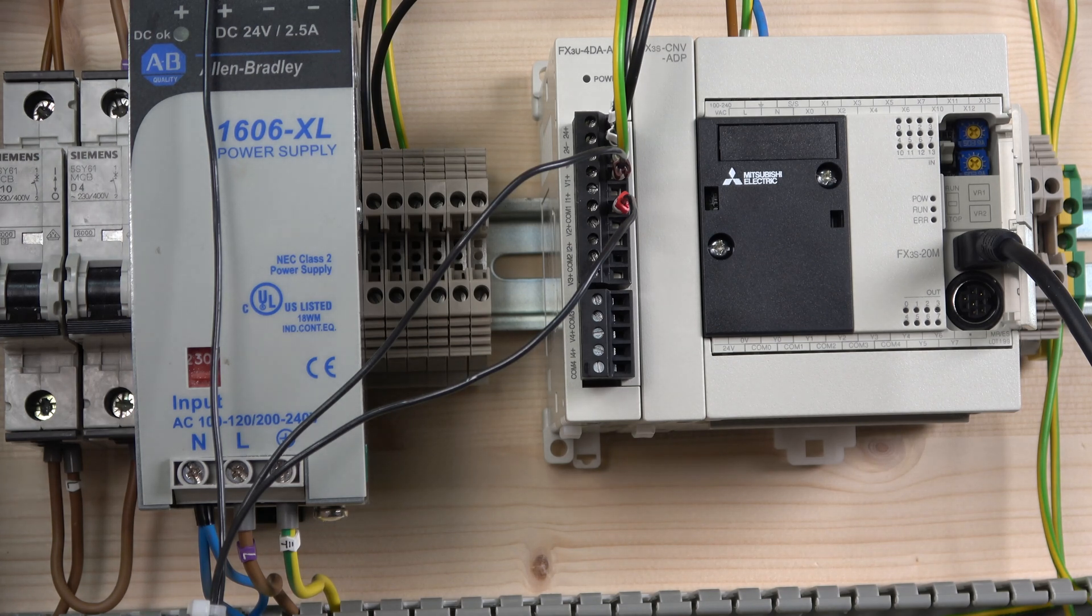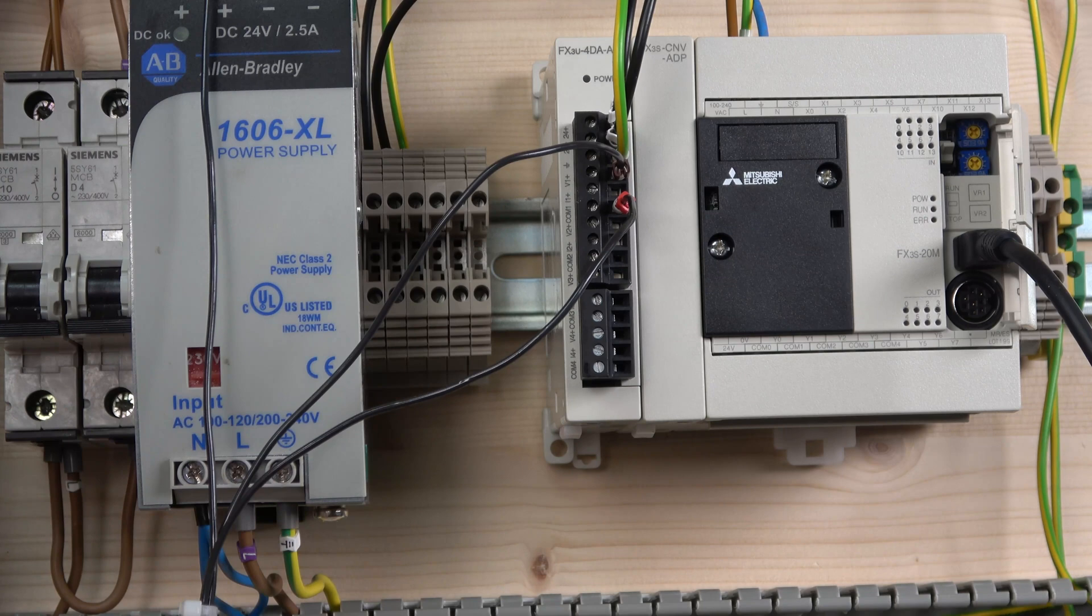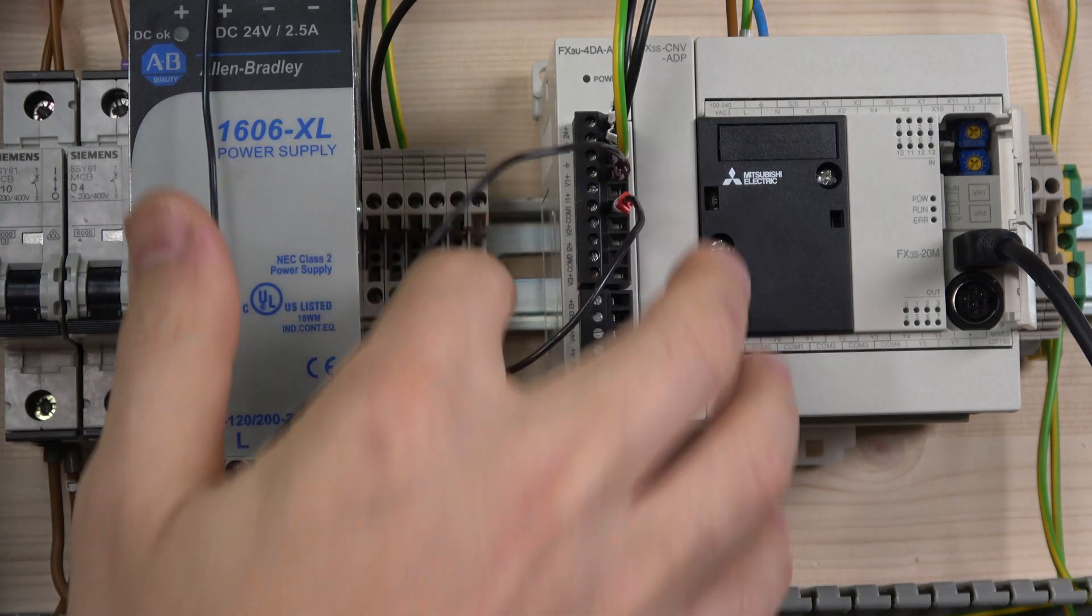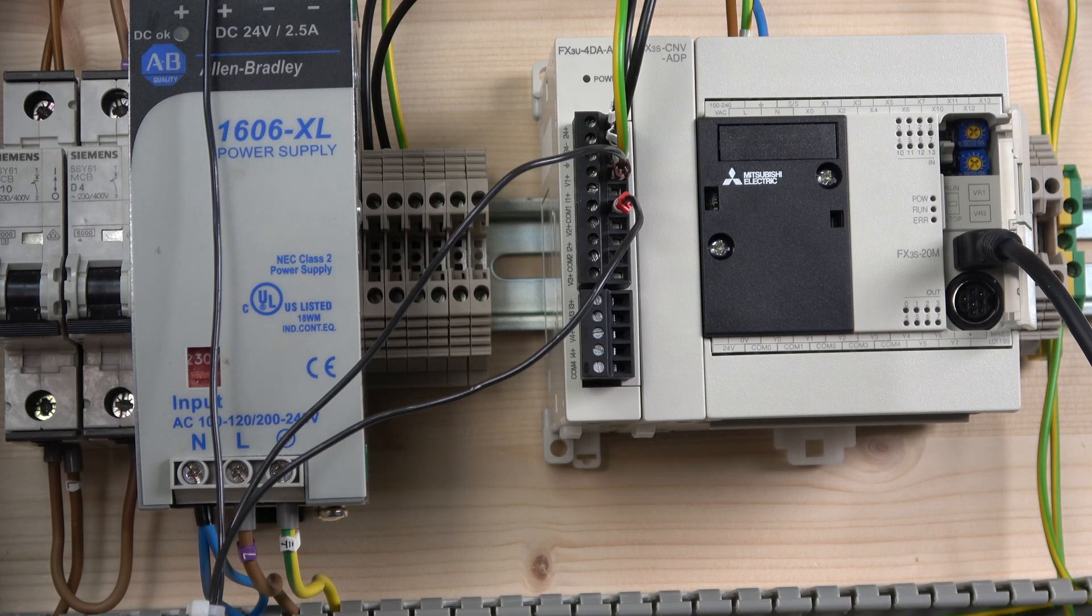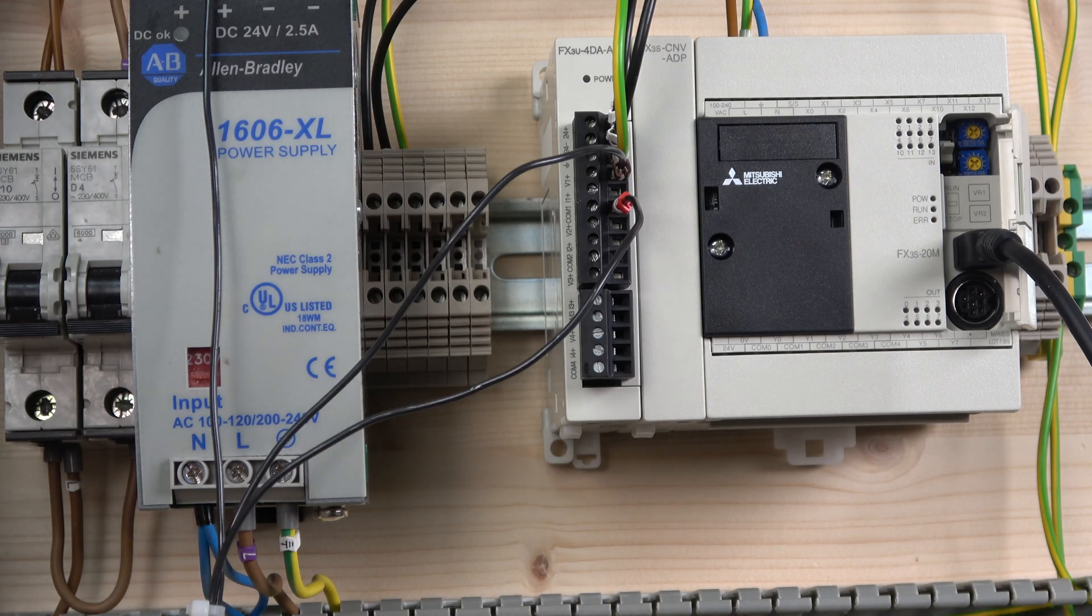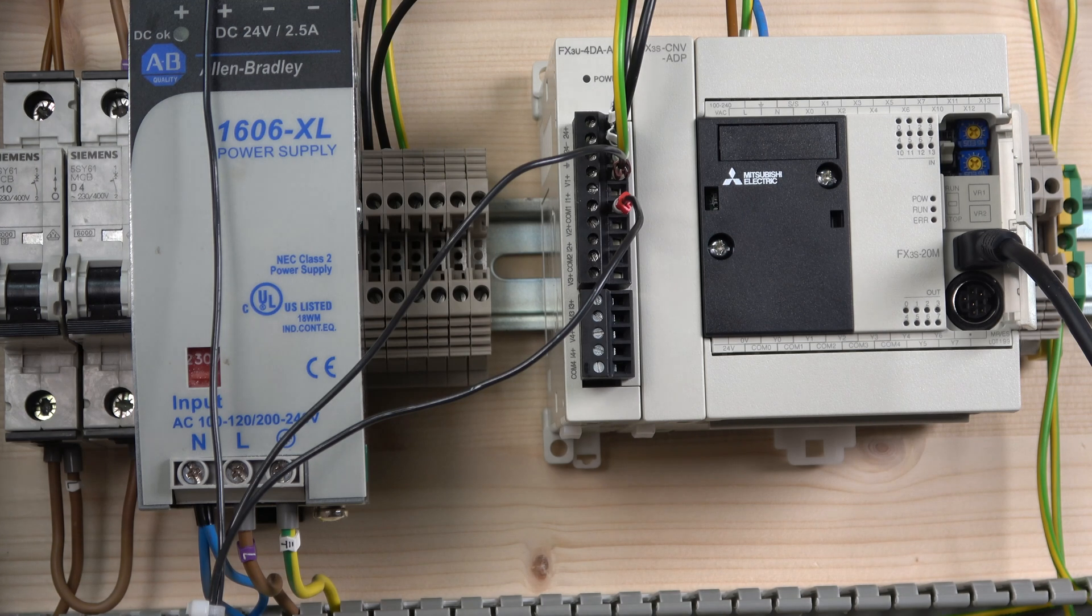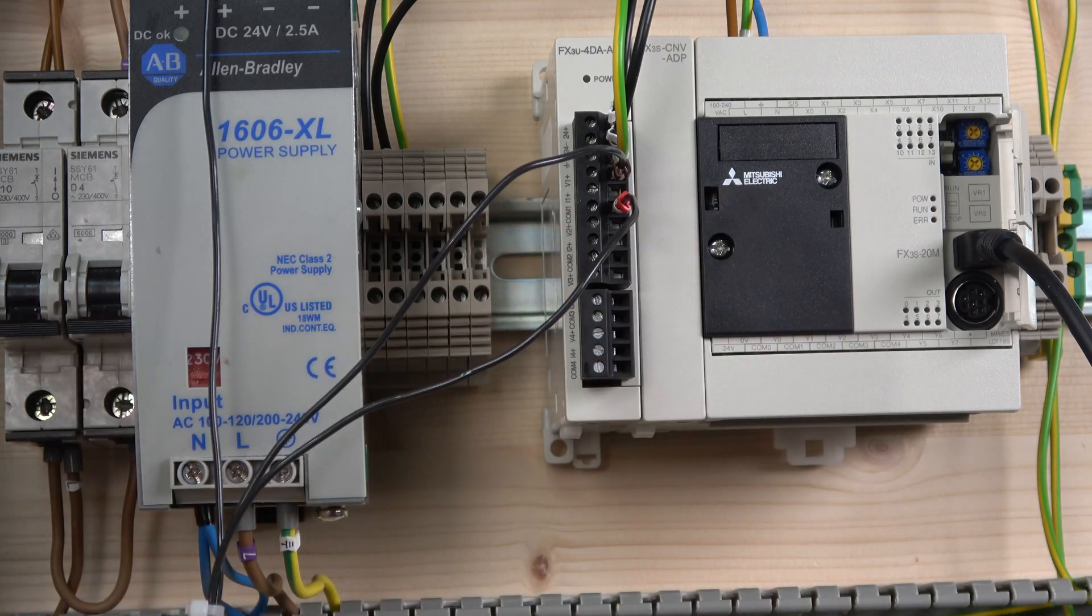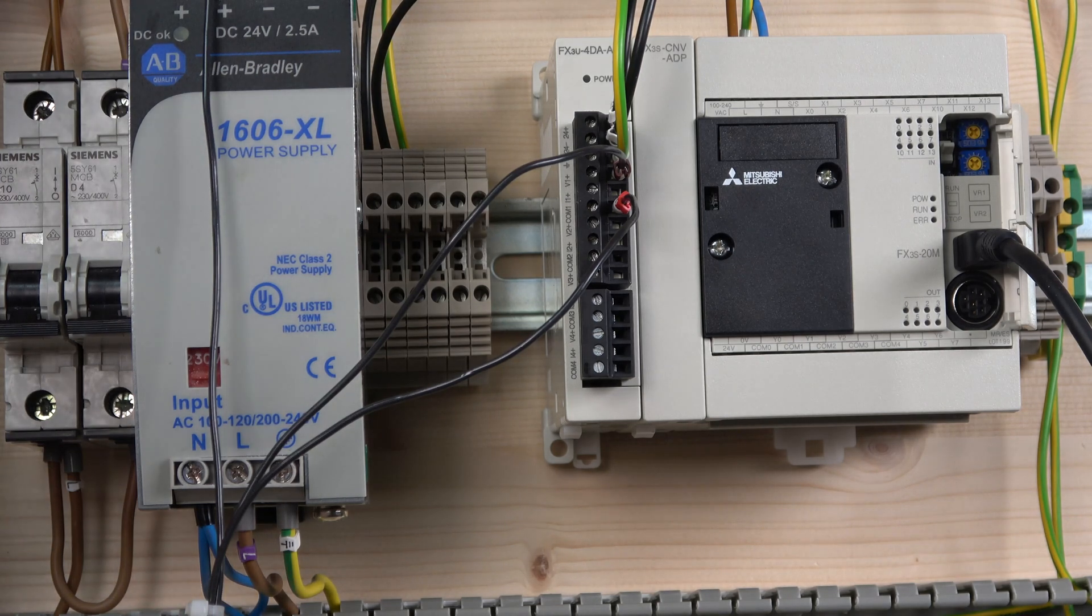You can control the drive, send the 0 to 10 volts in there, or you can have 4 to 20 milliamps out to some form of solid state relays to control your heating elements and things like that. We are going to be checking them out sometime in the future for some process setups. To get out the 4 to 20 milliamps, you need to make sure that V1 and I1 is joined together, and that way the PLC will understand what value it's supposed to reach there.